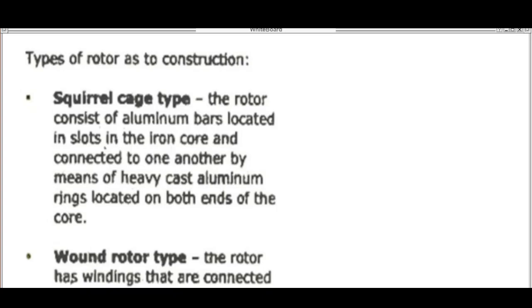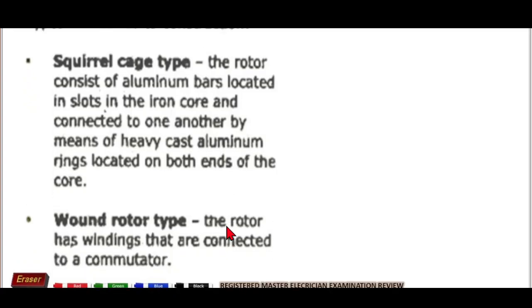So AC motors, we have two types of rotor construction in an AC motor. So the first one is squirrel cage. So para siyang cage ng squirrel. So ibig sabihin, it consists of aluminum bars located in slots with iron core connected to each other by heavy cast iron aluminum rings, no, on both ends of the core. Yung isa naman is a wound rotor. So the type of rotor windings that are connected to a commutator.